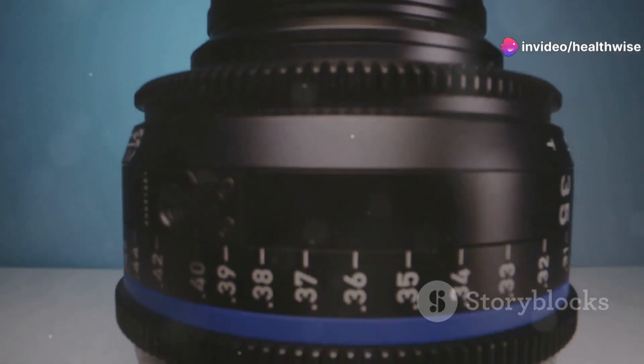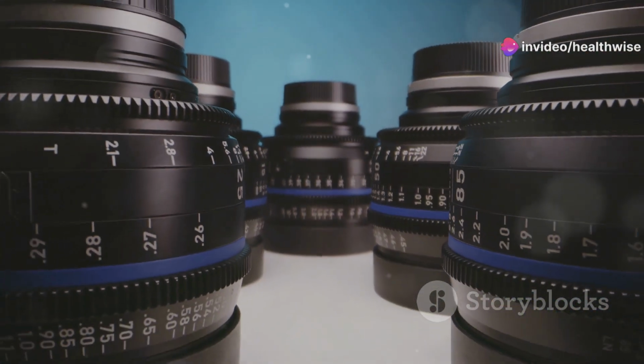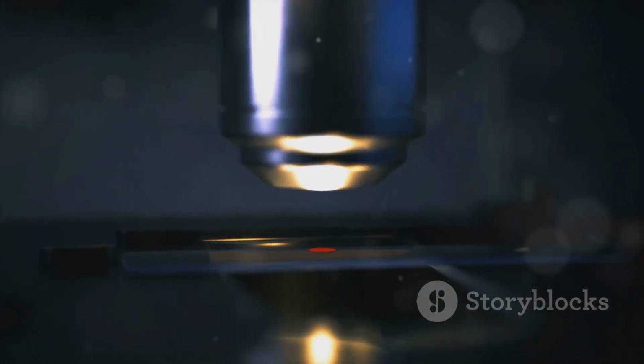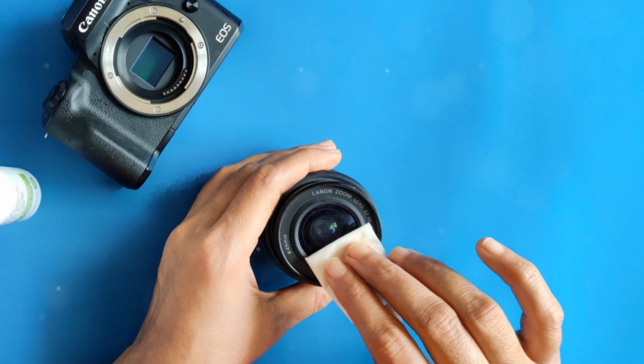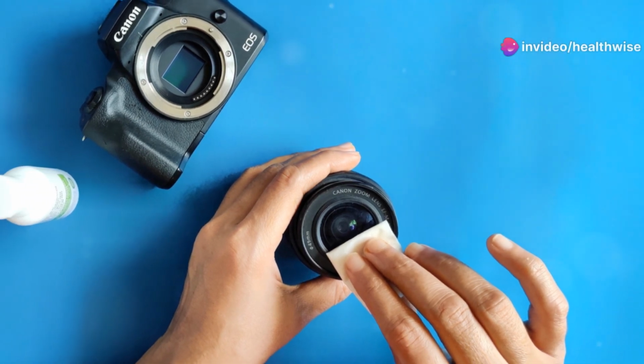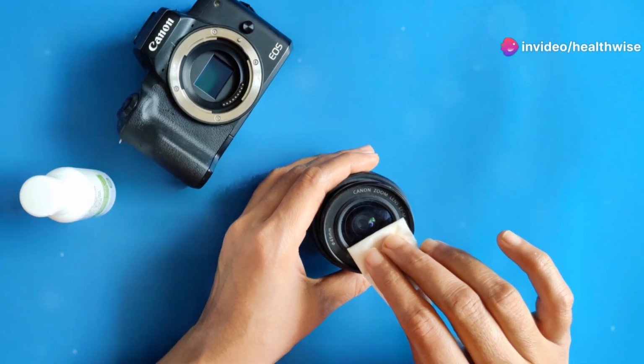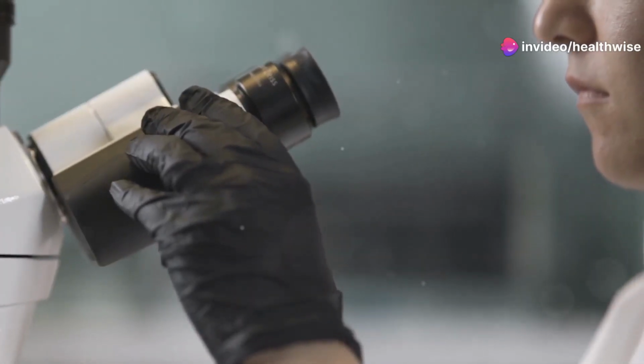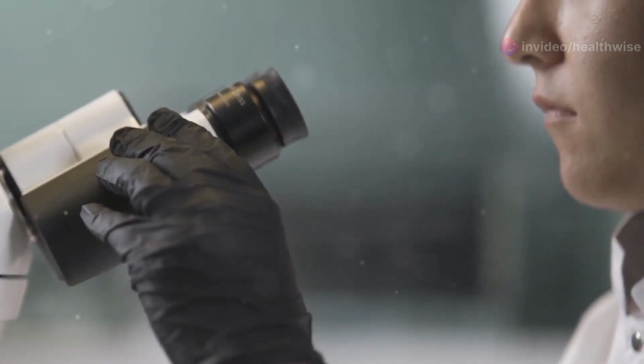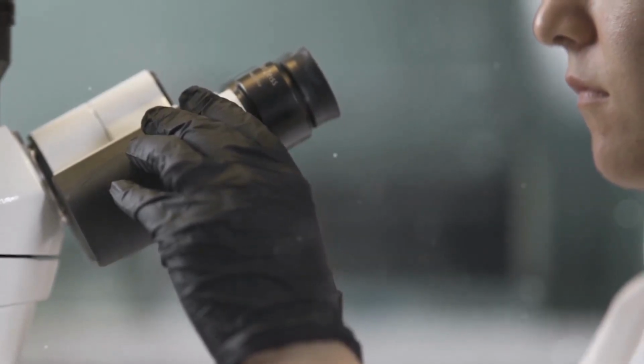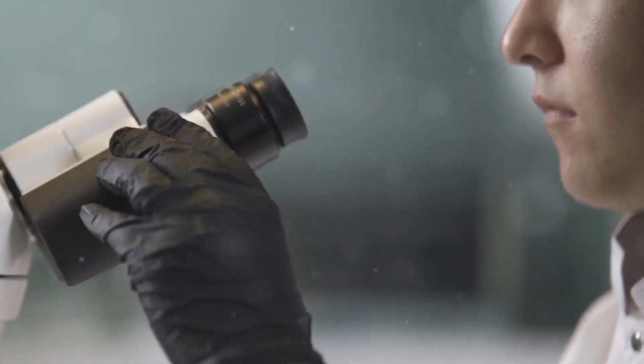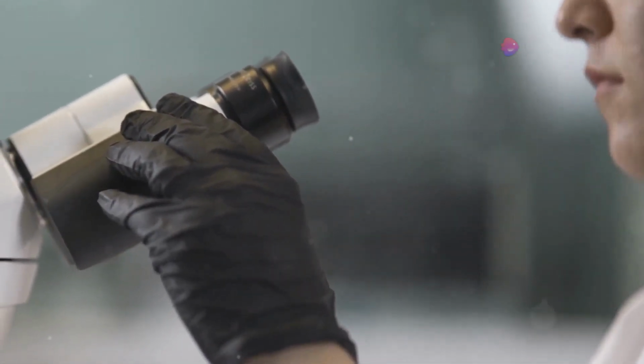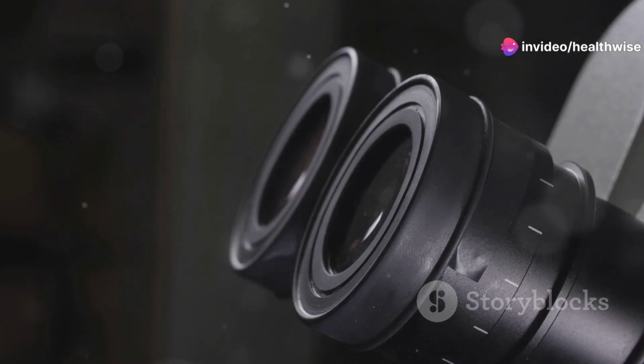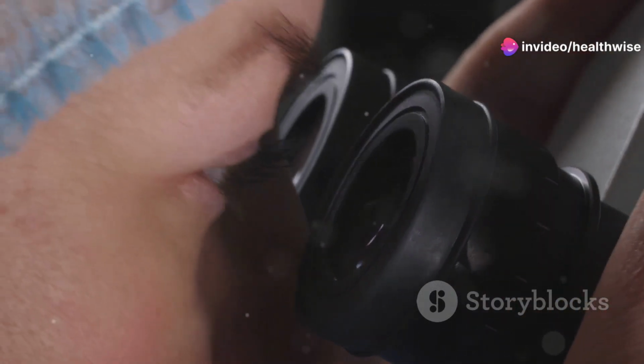Now, for this delicate task, we turn to a specialized solution, xylol. This solvent effectively dissolves oil and grease, leaving your objectives sparkling clean. But before you proceed, a word of caution. Avoid using alcohol-based cleaners on your objectives. Alcohol can damage the delicate lens coatings, compromising their performance. Instead, moisten a lint-free cloth with a small amount of xylol and gently wipe the objective lens in a circular motion. Remember, a clean objective lens is your gateway to a sharper, clearer microcosm.